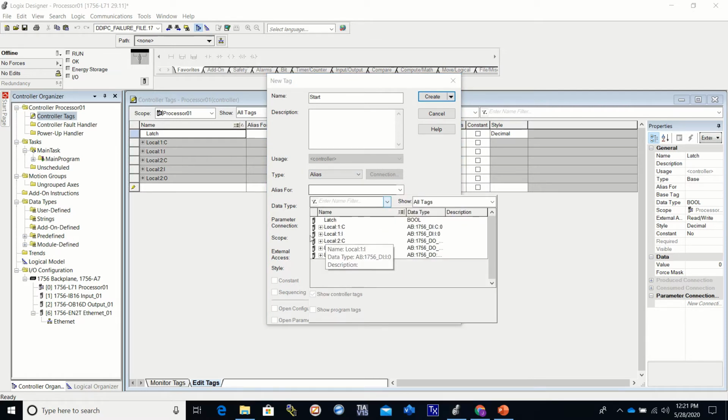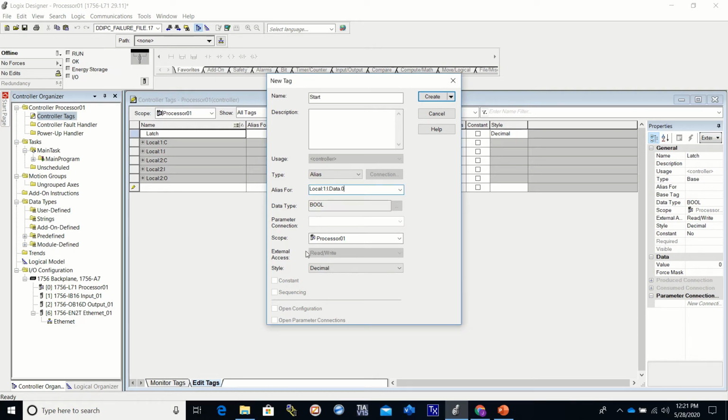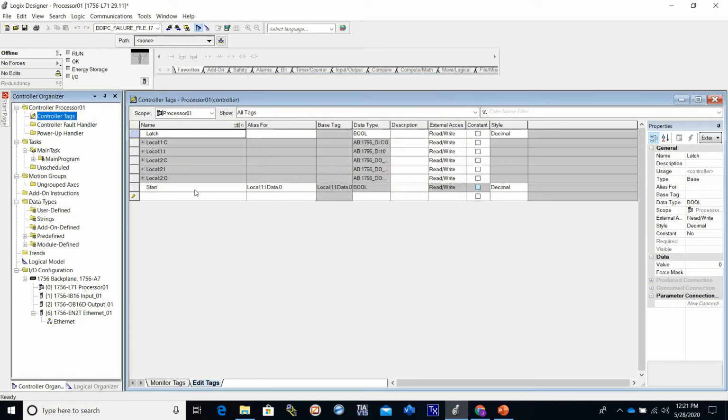We said that our input card is in slot one, so that's this one right here, Local:1:I data. And where did we wire it to on that card? Well, I'm going to go with zero, just so we start out using all of our numbers. I don't jump around. I like to use my numbers in order if possible. You'll see that it put it in as a bool. I'm going to create, and there it is right there.